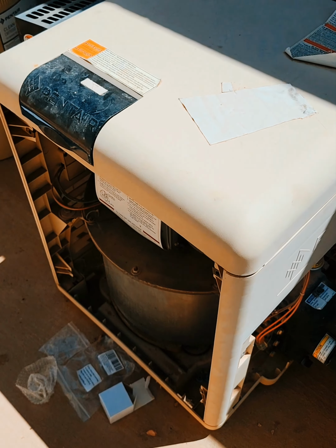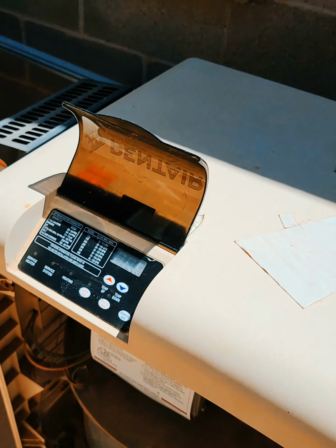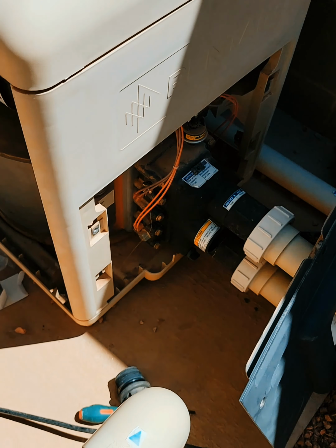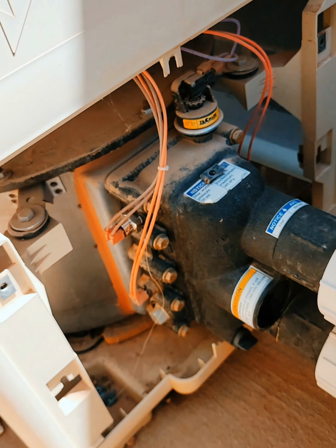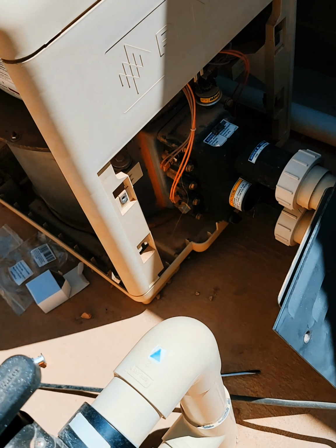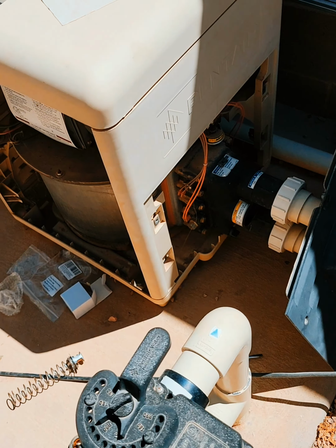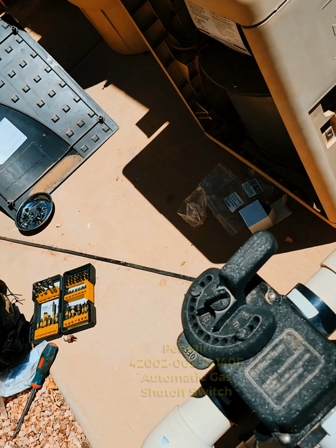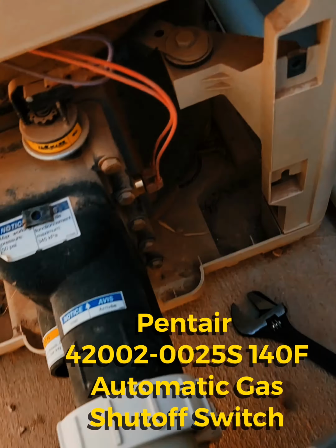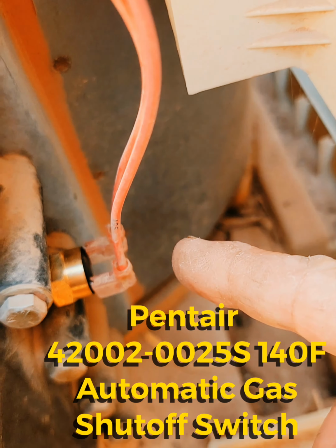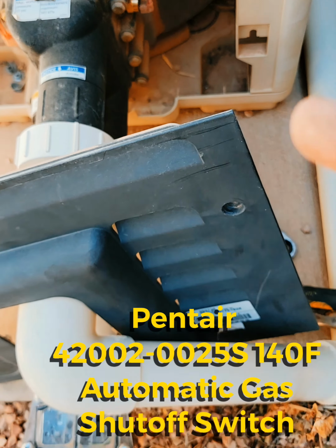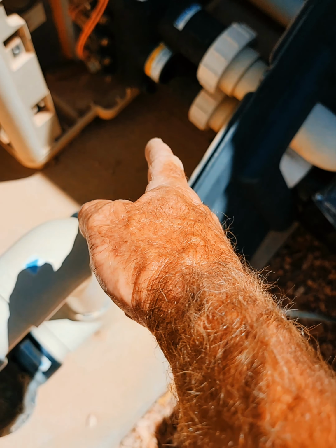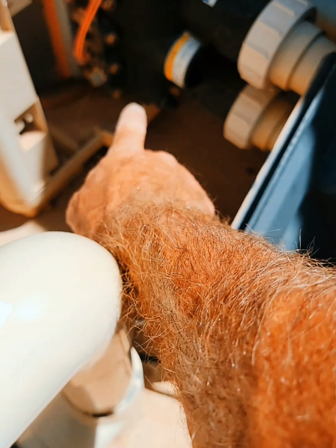So after replacing the CPU on this, which was needed because there was no display, and replacing the thermistor, which was not reading proper temperature, it's now giving me an error. It gave me the error code AGS, which stands for automatic gas shutoff. Which could be a couple of problems. It could be your AGS switch, which is right here, or possibly the high limit, but also the bypass valve inside there, if that's really bad.